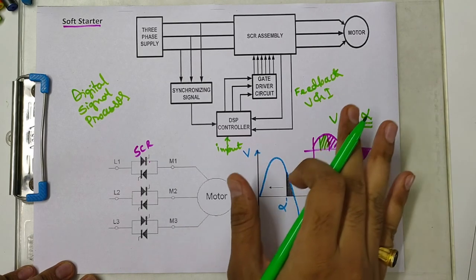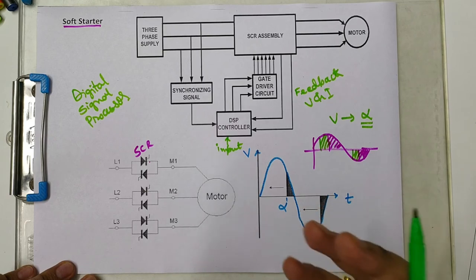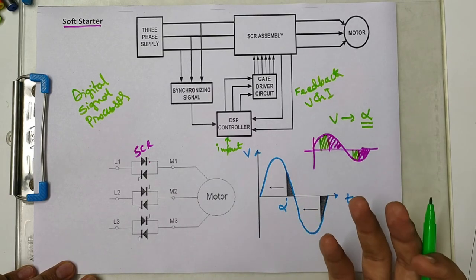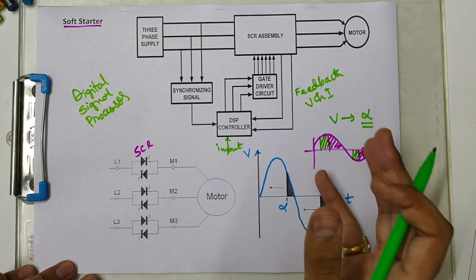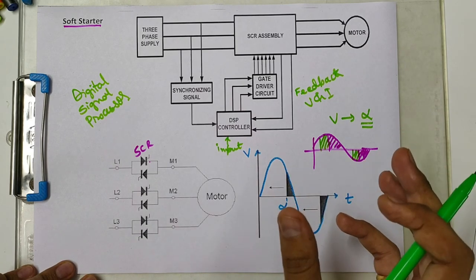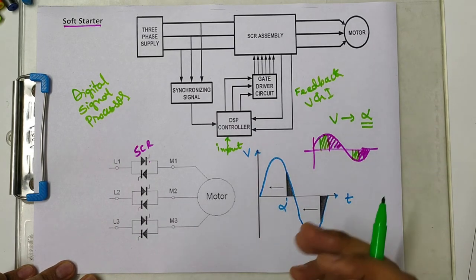The advantages of the soft starter include: it can be connected with any type of motor, be it star or delta. As it is a power electronics circuit, it does not use resistances or bulky reactors, so it does not require changeover switches and requires very little space.